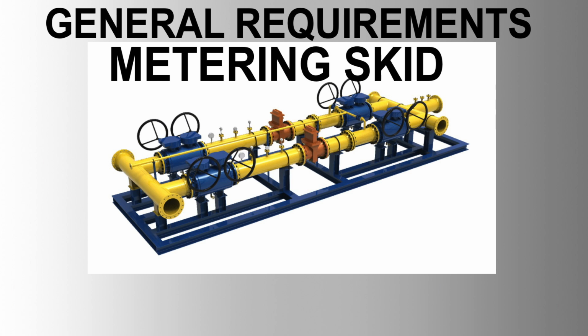Environmental protection. Instruments must be protected against environmental factors such as humidity, salt air, and corrosive atmospheres. Enclosures should provide appropriate levels of ingress protection, e.g. IP65 for outdoor unprotected installations. Instruments in potentially explosive atmospheres should comply with relevant IEC standards and be appropriately certified.